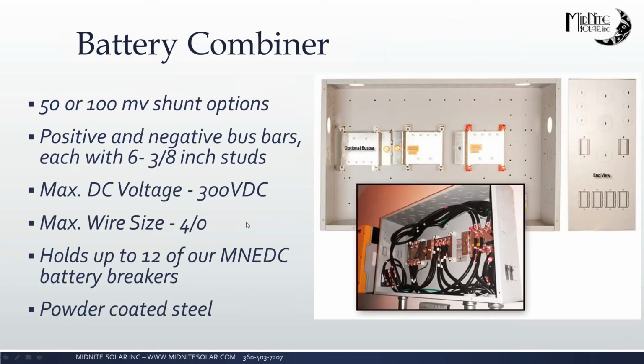All right, thank you, Sue. Yeah, the battery combiners basically come in two models. We have a 50 or a 100 millivolt shunt option. And basically there's a 1,000-amp shunt in there, and different battery monitors, different inverters use the different shunts. So you need to look at that. Like the Classic, for instance, would use the 100 millivolt 1,000-amp shunt. So that's pretty clearly called out on our website, but definitely make sure you're picking the right one for the inverter you're using.